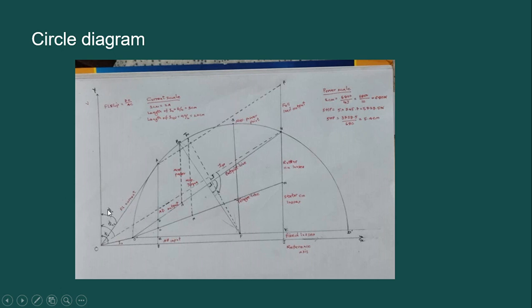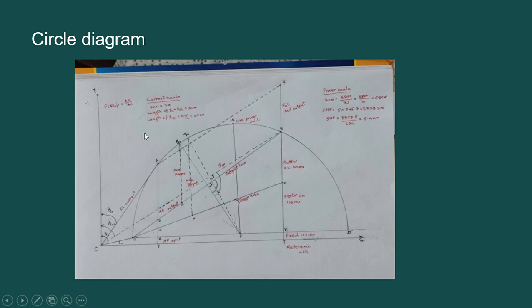The angle phi L between the full load current and the voltage reference gives you the power factor at full load. From this circle diagram, we can also calculate the full load slip. To calculate that, measure the length of DC divided by the length of AC — this gives you the full load slip.